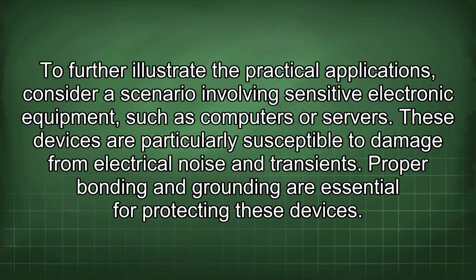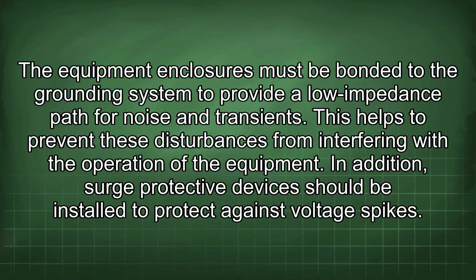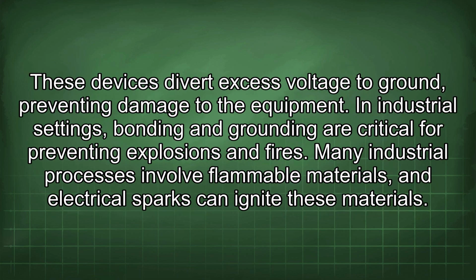To further illustrate the practical applications, consider a scenario involving sensitive electronic equipment such as computers or servers. These devices are particularly susceptible to damage from electrical noise and transients. Proper bonding and grounding are essential for protecting these devices. The equipment enclosures must be bonded to the grounding system to provide a low impedance path for noise and transients. This helps to prevent these disturbances from interfering with the operation of the equipment. In addition, surge protective devices should be installed to protect against voltage spikes. These devices divert excess voltage to ground, preventing damage to the equipment.